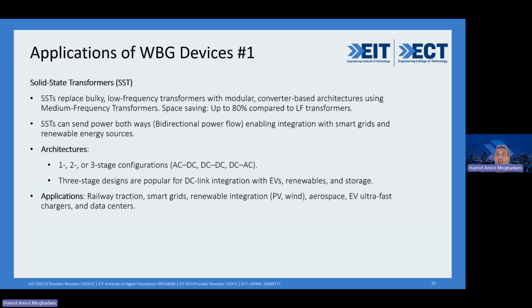A little bit about the architecture of this SST: it is usually based on a 1, 2, or 3-stage configuration. Let's talk about the 3-stage configuration. The first stage is AC to DC, converting medium voltage AC coming from your grid to medium voltage DC. Between these two stages, you have your DC link.